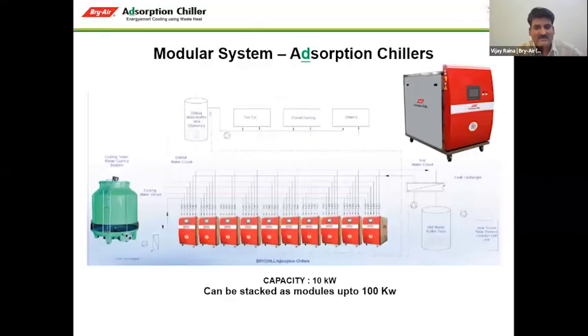The smaller ones can be stacked for 50 kilowatt, 100 kilowatt, depending on the heat load available at site. For commercial application, mainly we depend on solar or any other heat source available from a CHP system. So frankly, for commercial, if you look at the solar renewable cooling solution, we can stack it as 50 kilowatt up to 100 kilowatt also.